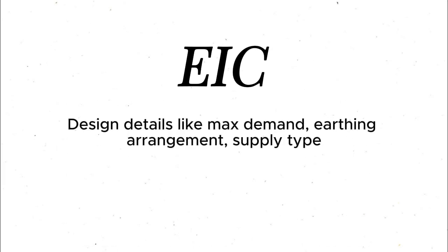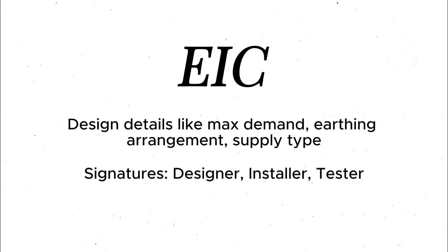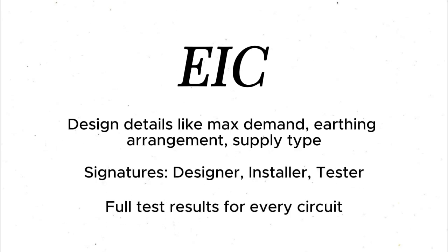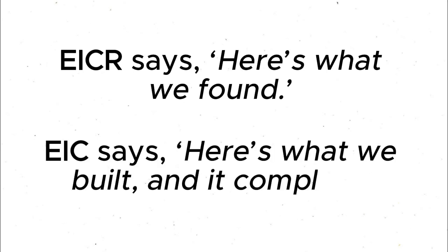EIC includes design details like max demand, earthing arrangement, supply type. Signatures, designer, installer, tester. Full test results for every circuit. In short, EICR says, here's what we found. EIC says, here's what we built, and it complies.